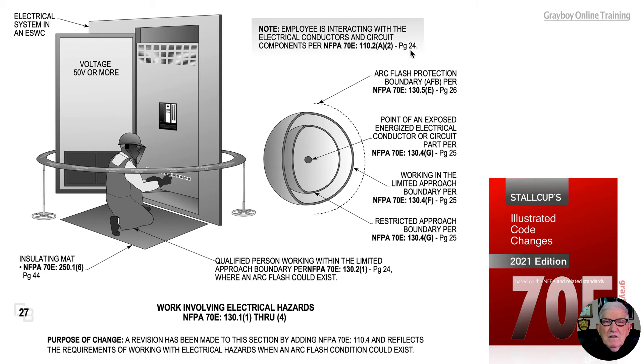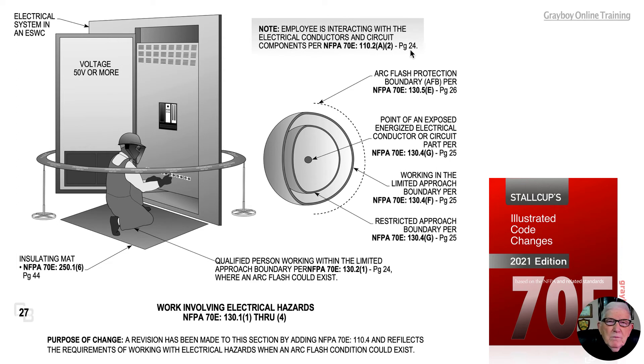As stated, "interacting" — if you look at the definition of "working on" in Article 100 of 70E — means you're interacting in some way with the equipment: switching the equipment, switching a circuit, and so forth, maybe changing out a circuit breaker or other electrical component that had failed to function in some way.